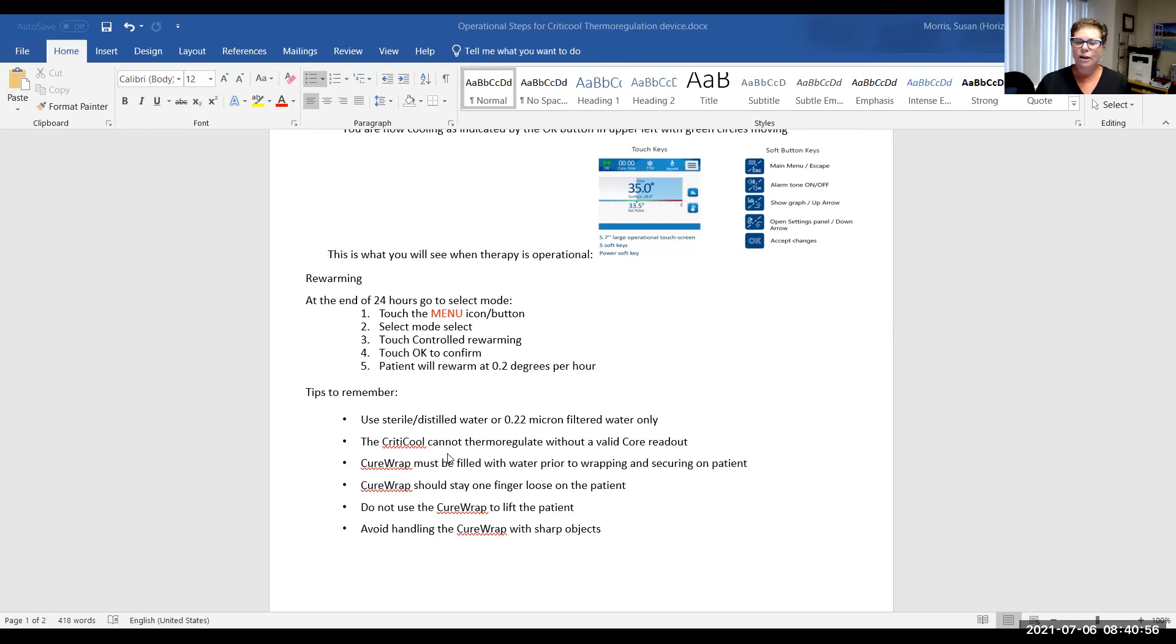So only use sterile or distilled water. You cannot use this device without a core temperature. It needs that feedback. The CureWrap must be filled with water prior to wrapping it and securing it on the patient. You do not use a CureWrap to lift patients and try and avoid anything sharp because it will puncture a hole and then you will have to get a new CureWrap.